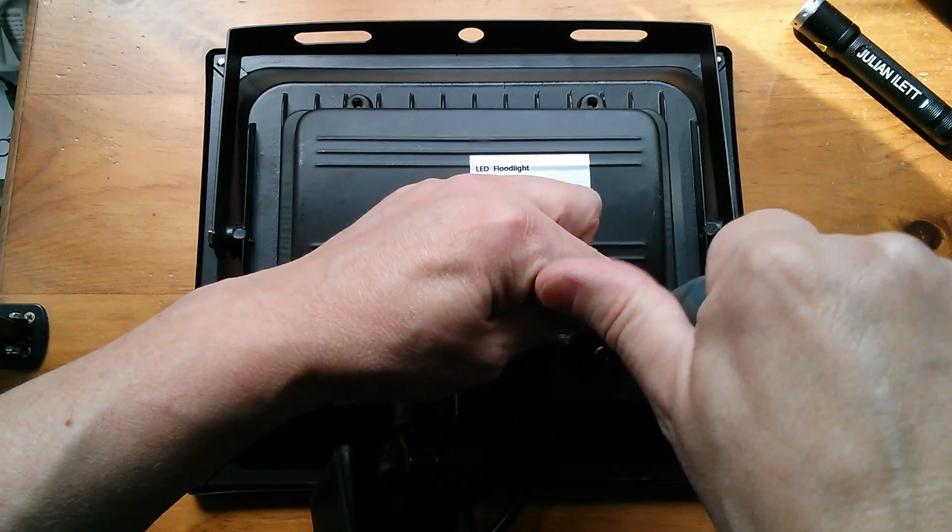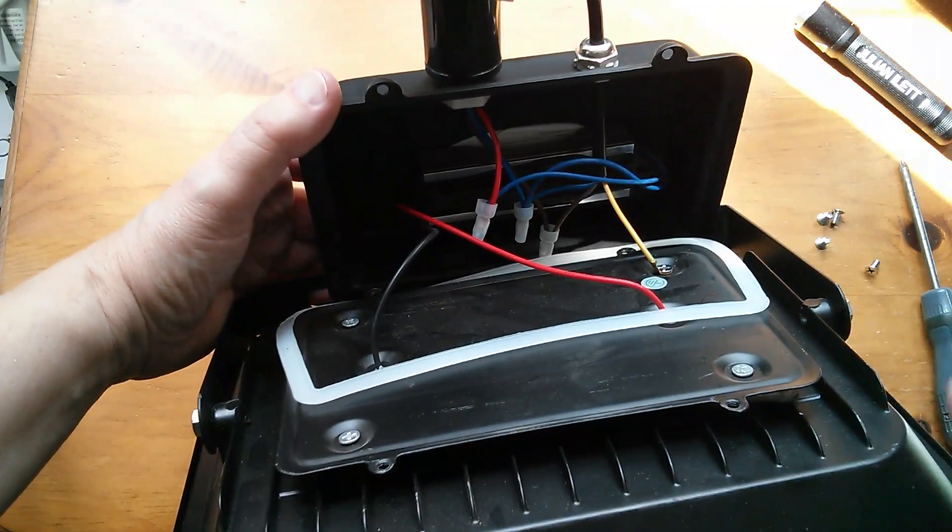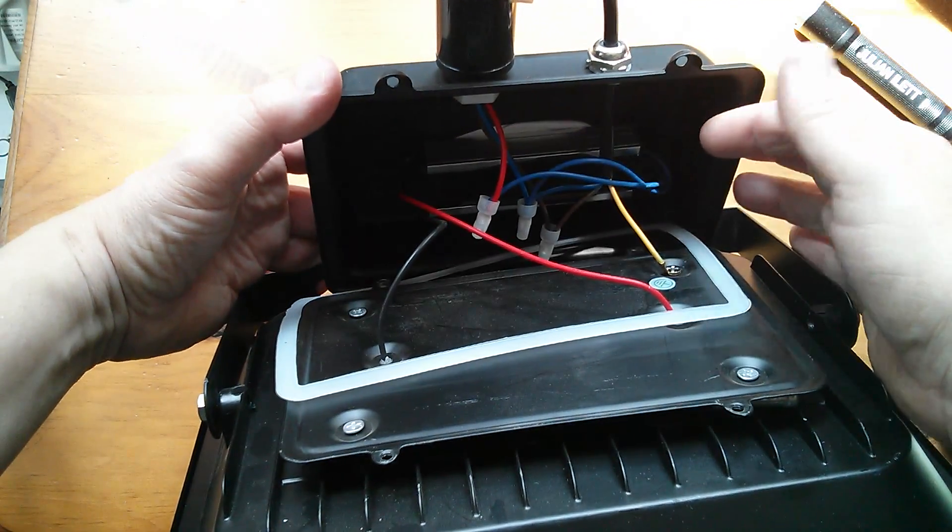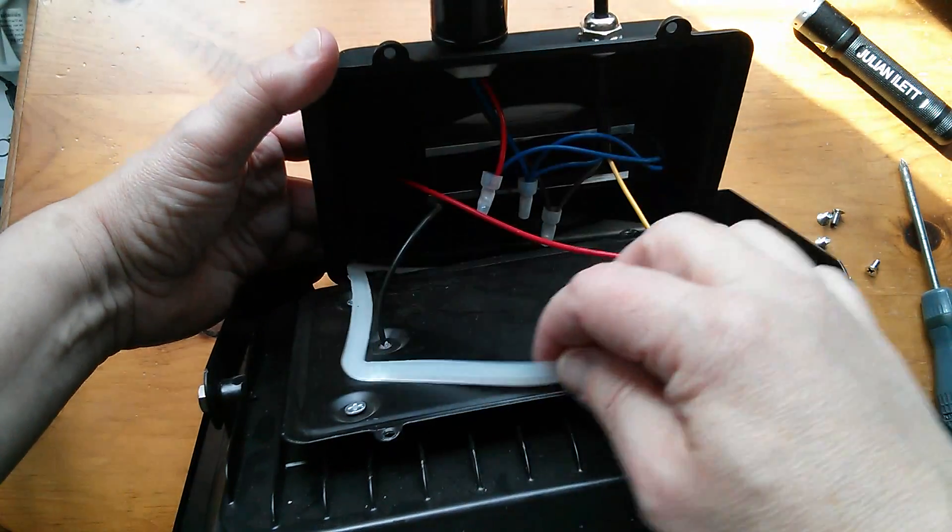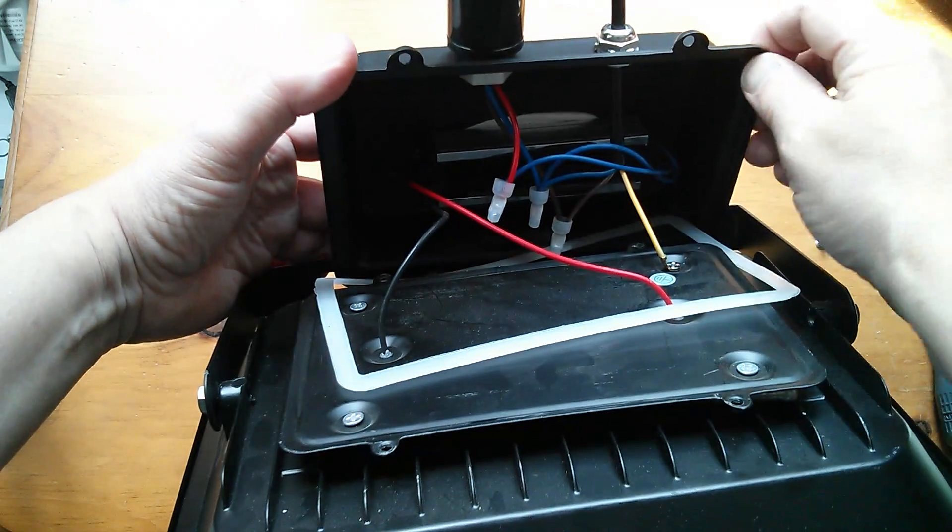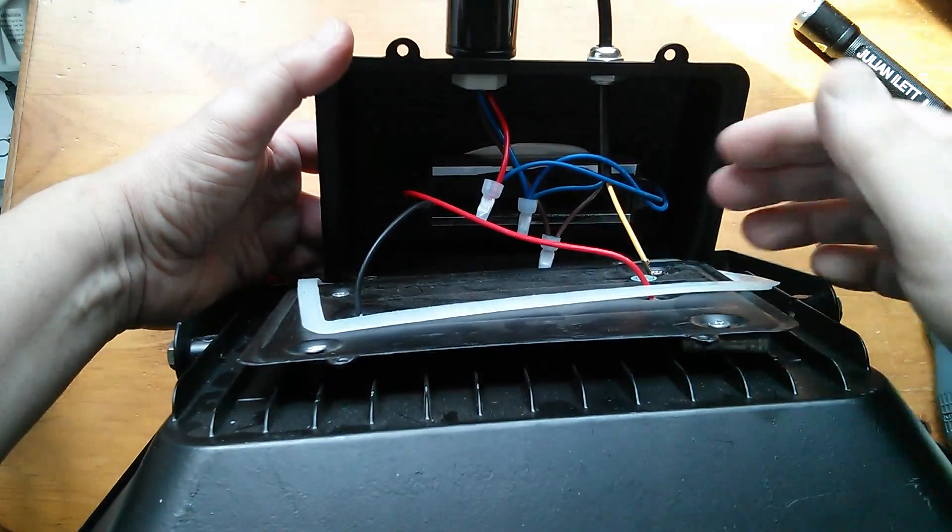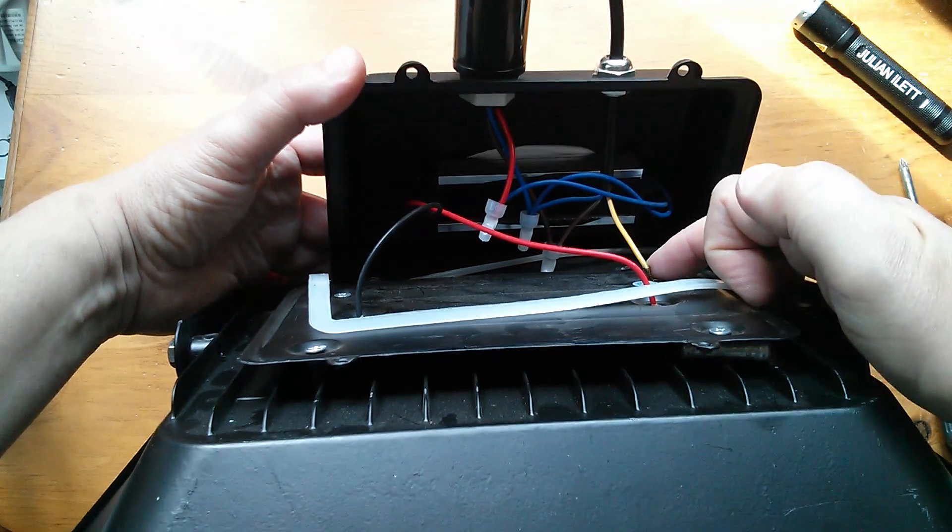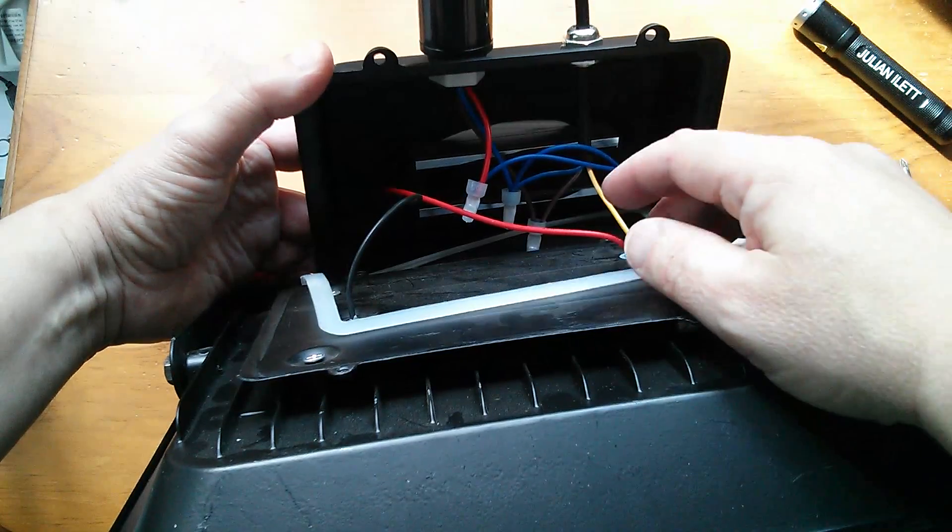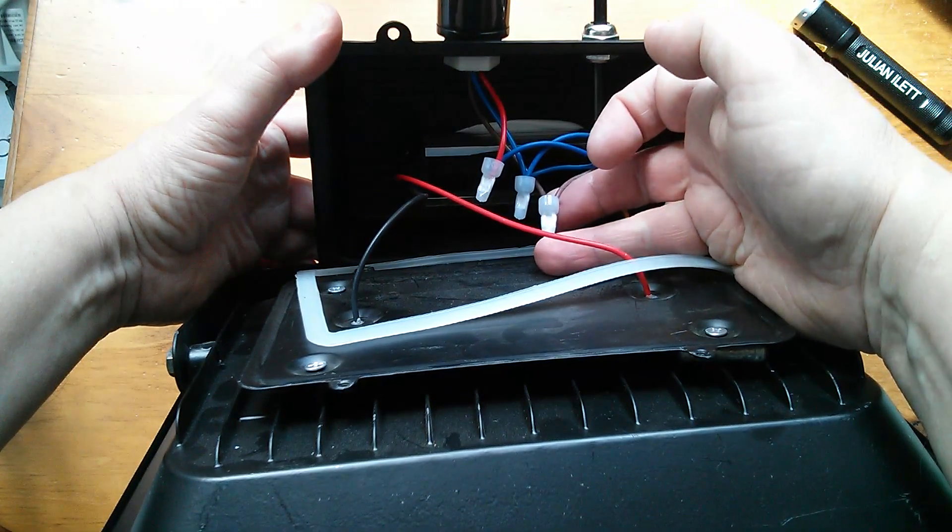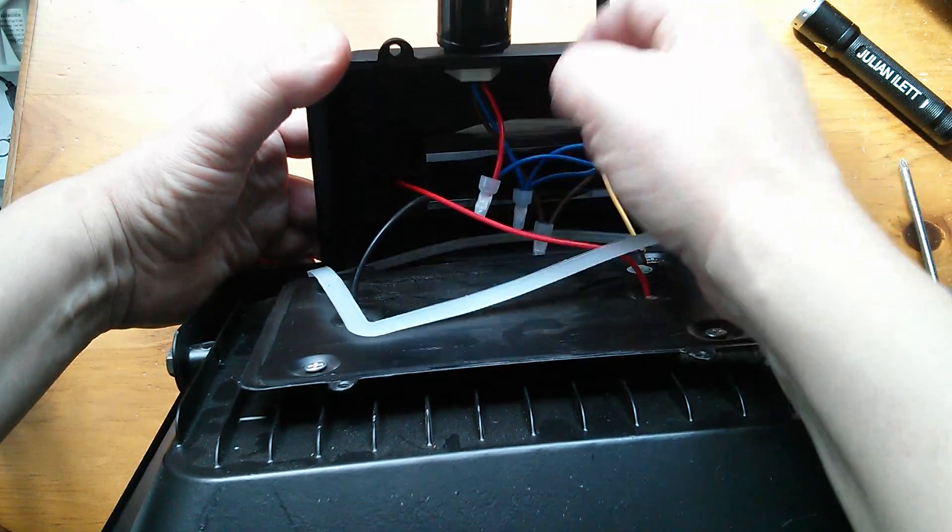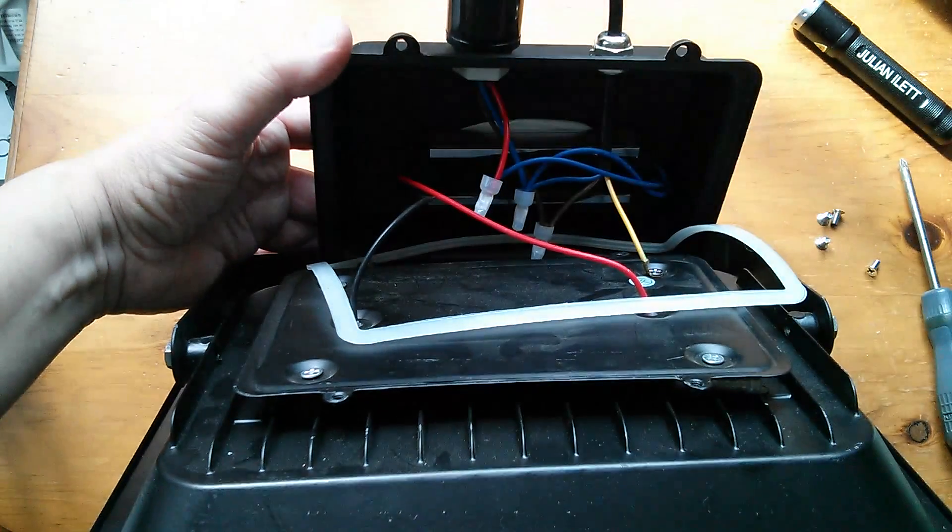Right, let's take this steel housing cap off first and see what's inside this rear part. Right, the wires are so short in here that I can't tip this back on itself, so I've had to tip the whole thing up on end. There's a gasket here which you have to sort of get in the right position so that this traps down on it and keeps the water out. Here's the incoming three pin cable. The earth is connected, as it really should be, with a metal box. You've got these twist connectors for live, switched live from the PIR sensor, and neutral.